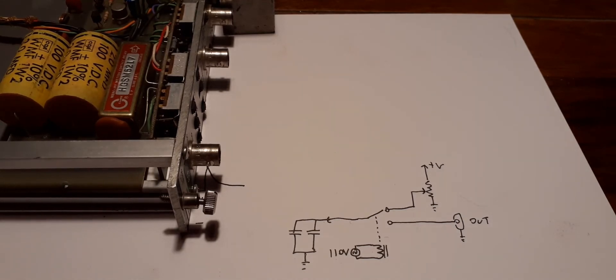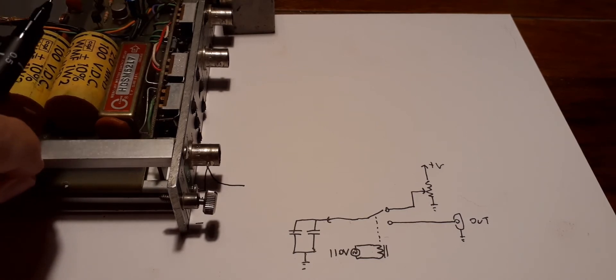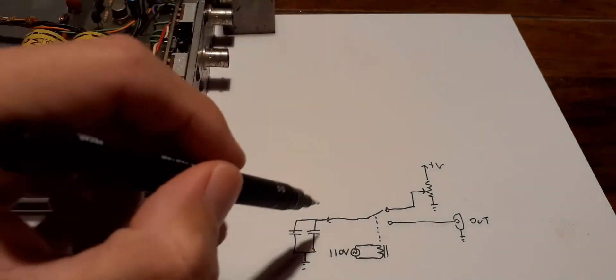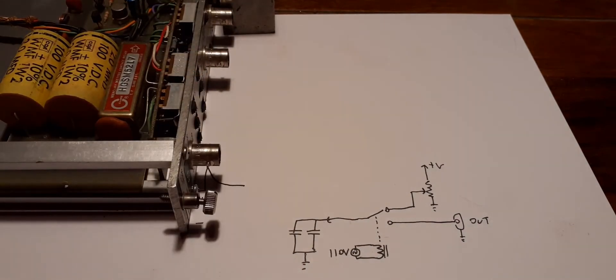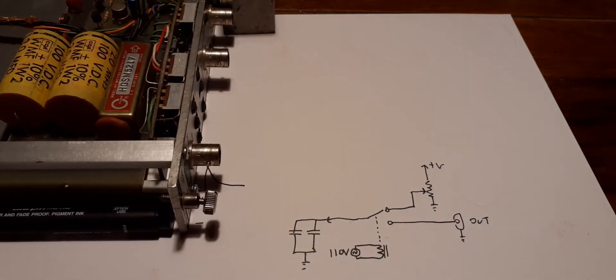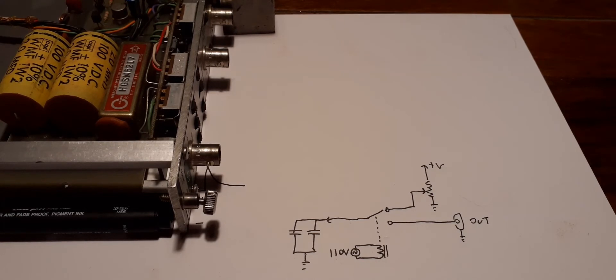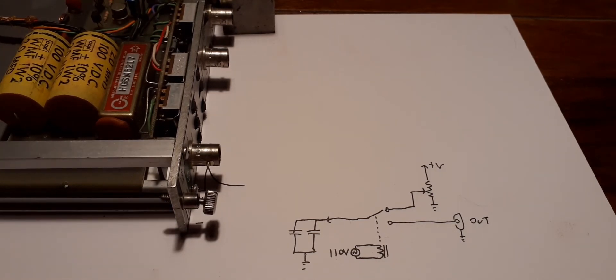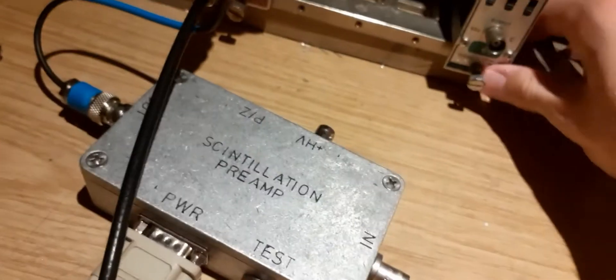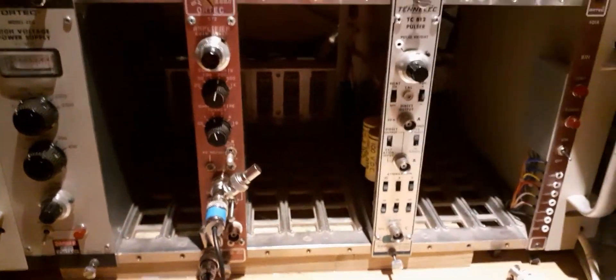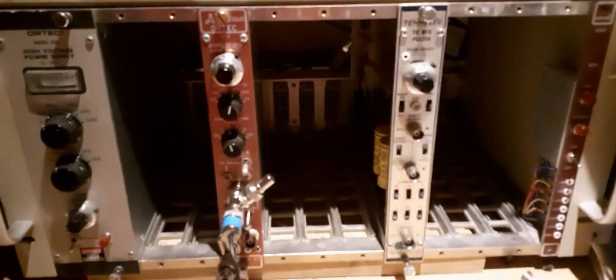A useful feature to calibrate your system is that it has provisions for an external voltage and an external relay driver, so you can set your own random gate generator to give a random pulse count each minute with a random voltage for a true simulation. But it might be interesting to see it actually in operation, so one second.